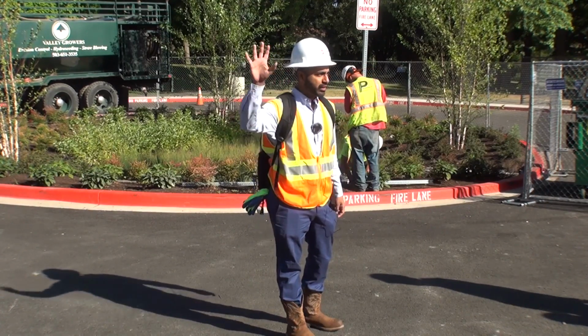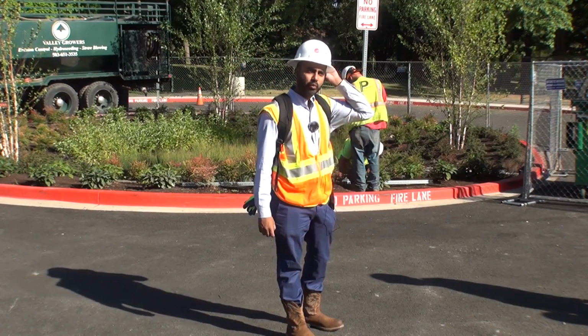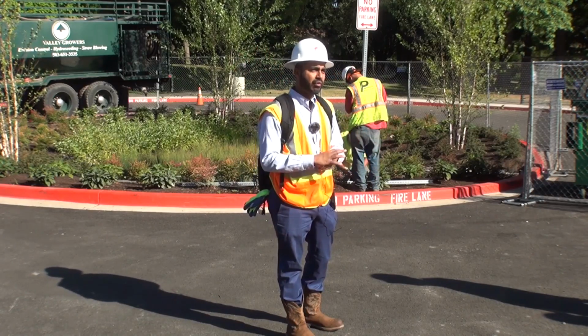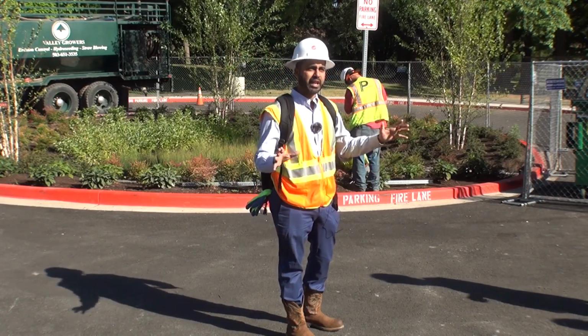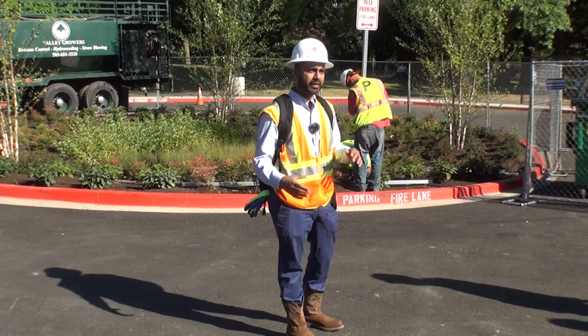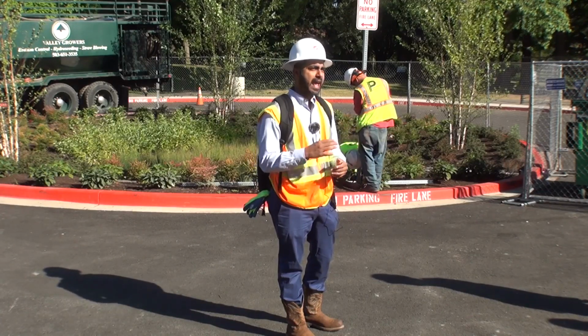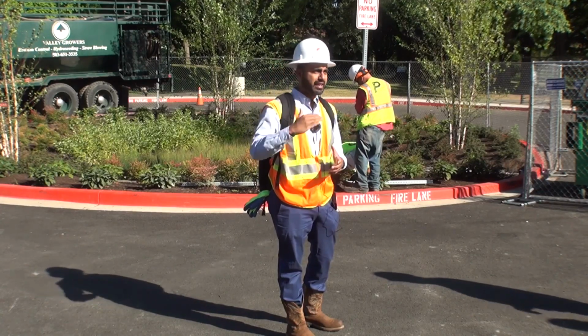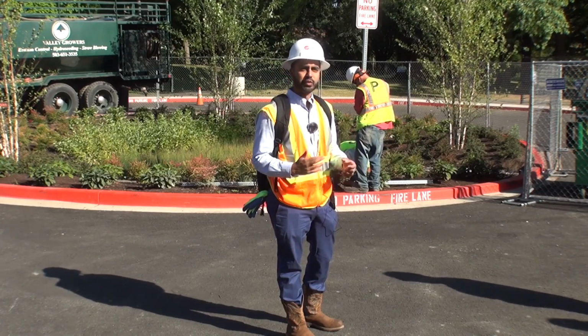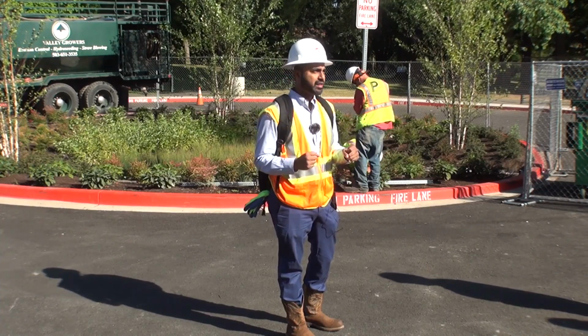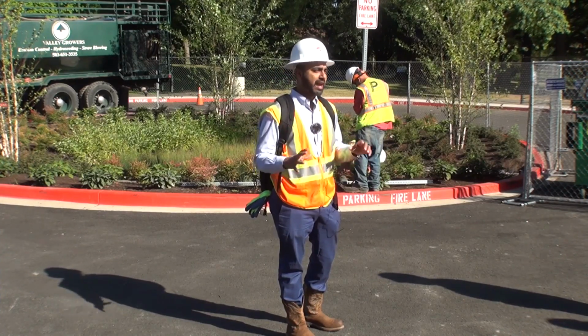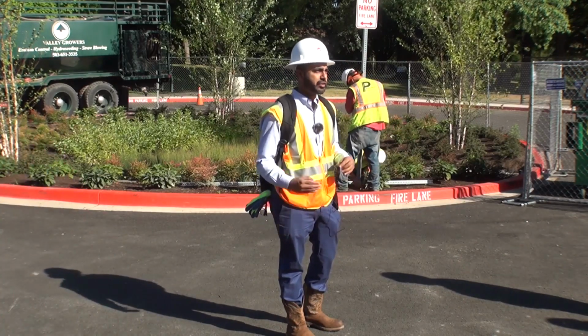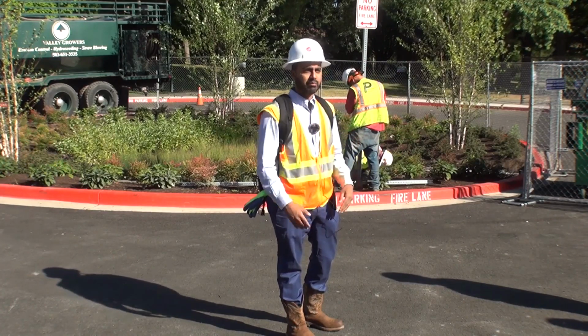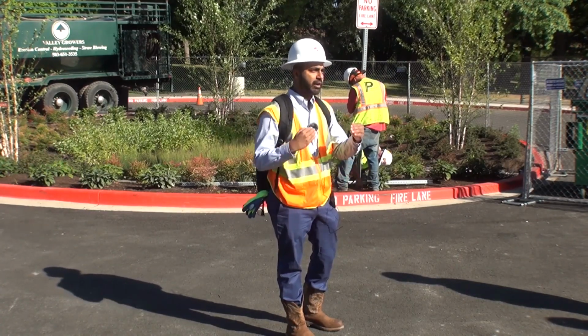They're mainly used to be cooling our server rooms over here, and they work a little bit differently than what you would expect traditional kind of split equipment to work. They have inverter compressors, so they can actually modulate from 90% of their capacity down to 10% of their capacity. So it's an always-on sort of system. It never has to turn off the fan or the outdoor condenser unit. It always runs at a very low speed, so they can match the load in real time. If ever you have a spike in the load, it can actually ramp up and ramp down.